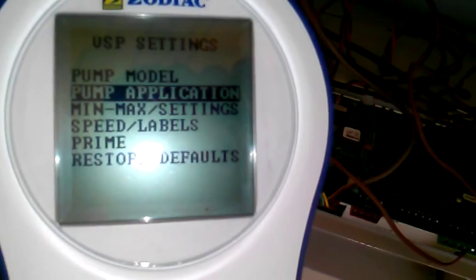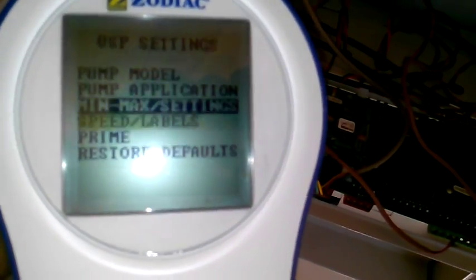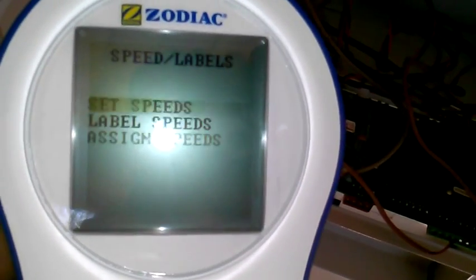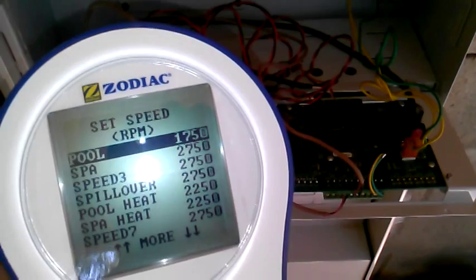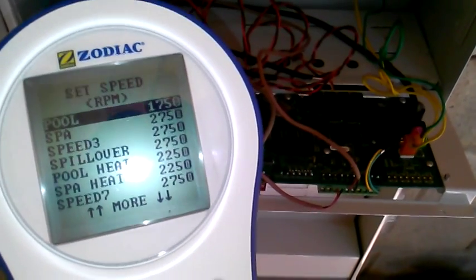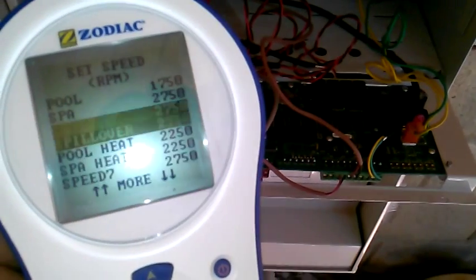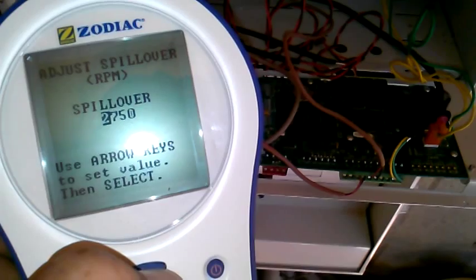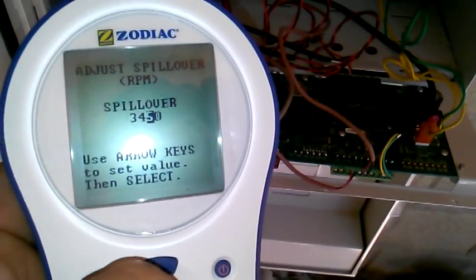You've also got your min and your max speed, priming, stuff like that. The next thing I'm going to do is set the speeds. Basically it's got a bunch of preset speeds — you're preset from 1750 for the pool up to 2750 for the spa, and all that's going to work. I might set the spillover higher since I've got a separate jet pump. I might want the spillover to be nice and high because this has a waterfall that goes between the spa and the pool.